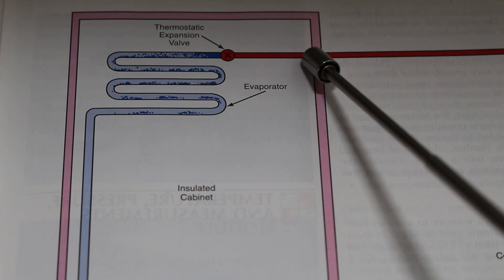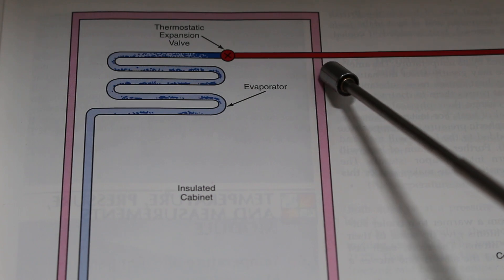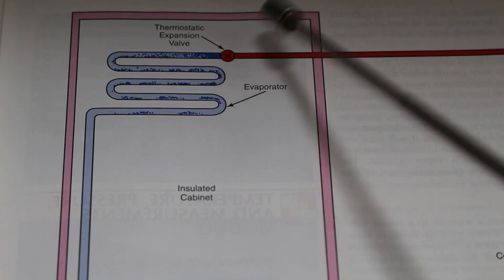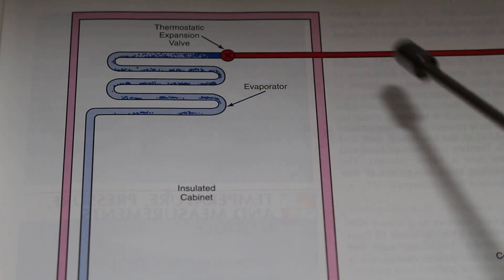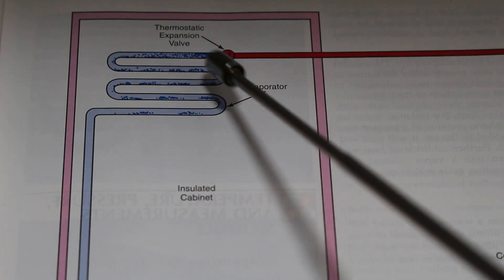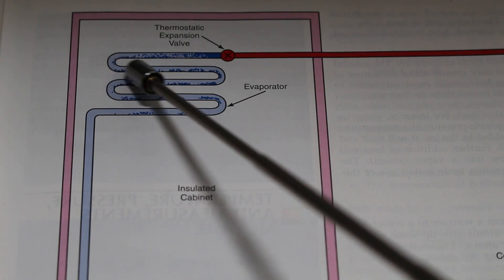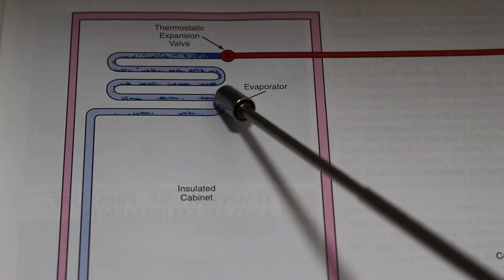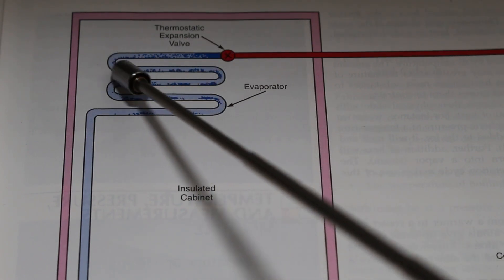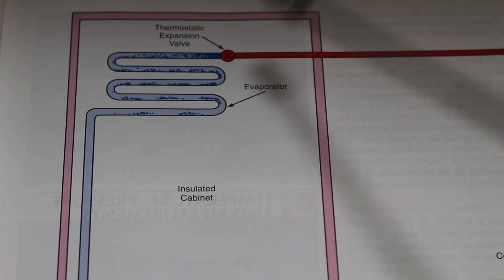If we look at the red tubing, this stands for our liquid line, which is our high pressure, high temperature, subcooled liquid leaving our condenser. And this piece here that is circular with the X in the middle is our expansion device. We have a dark blue here, and as it leaves our evaporator, we have a light blue — this is our liquid changing into a vapor. So the dark blue, we are still partially a liquid, and as we travel along our evaporator, we change state. That change of state is latent heat.